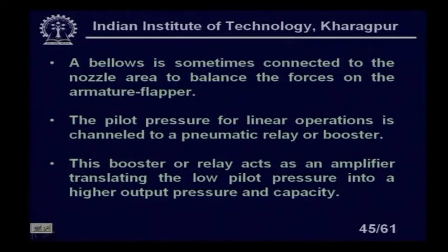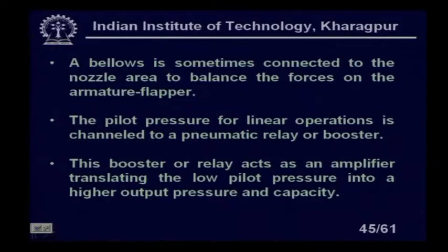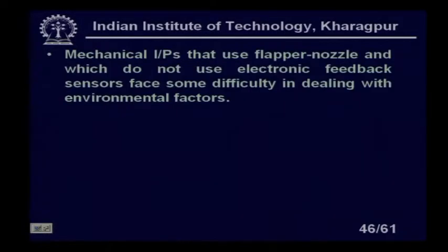The booster or relay acts as an amplifier, translating the low pilot pressure into higher output pressures and capacity. Okay, because the capacity is also important, because the capacity of this system might be very, very small. In this case, we have higher capacities, we can use both the capacity and range, I can go to the booster circuit or relay circuit.